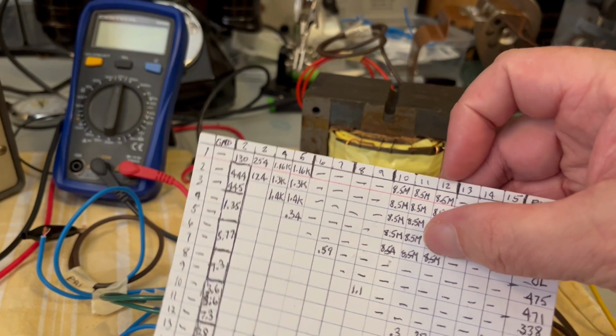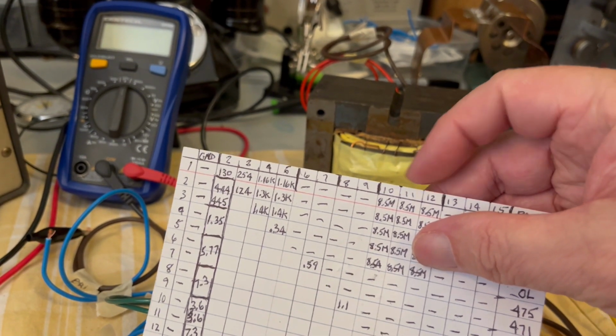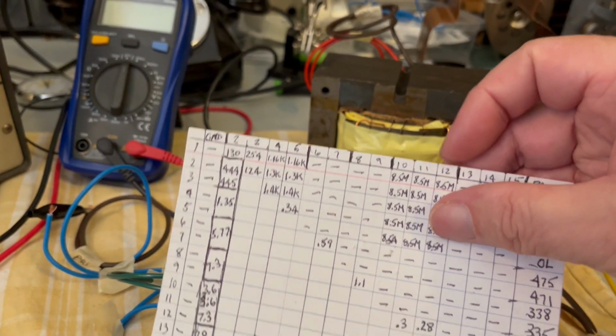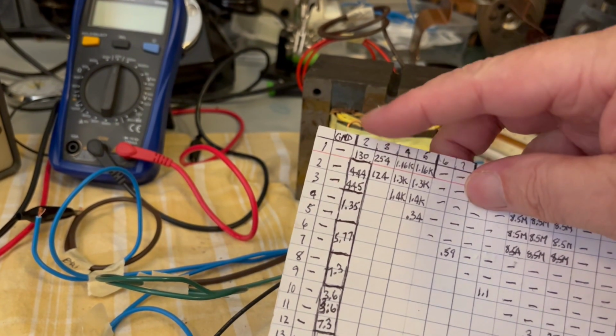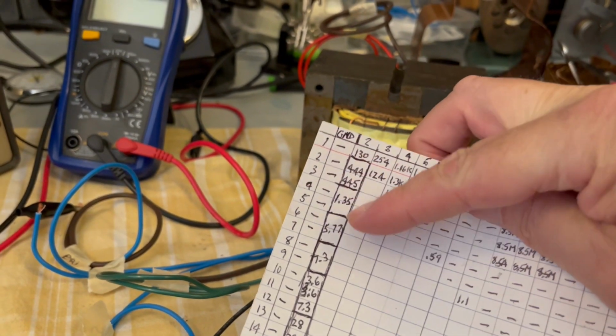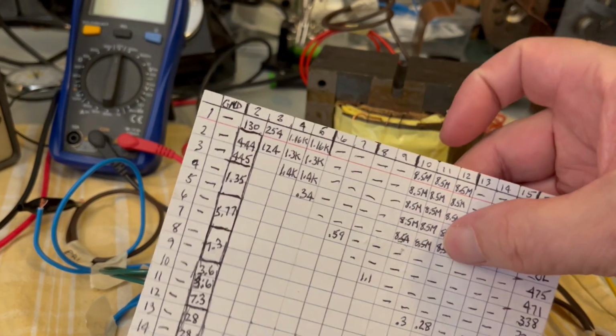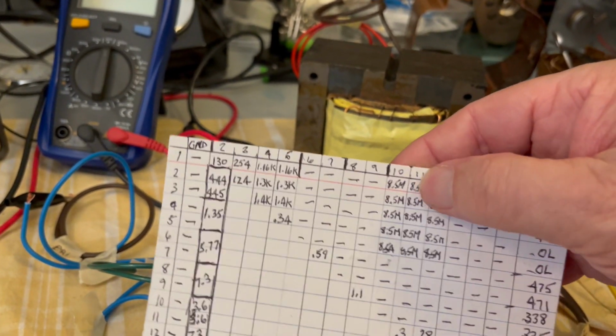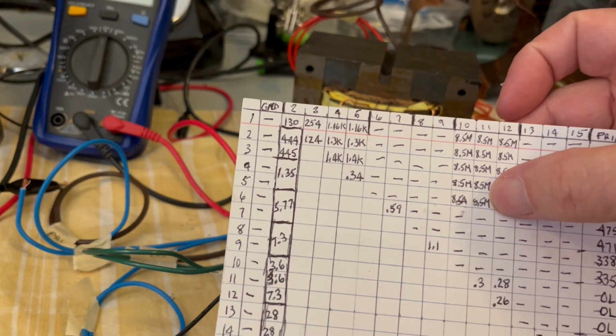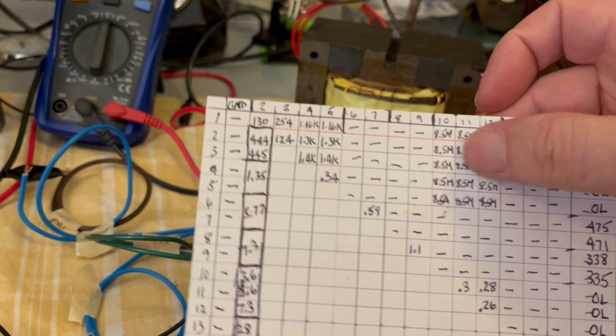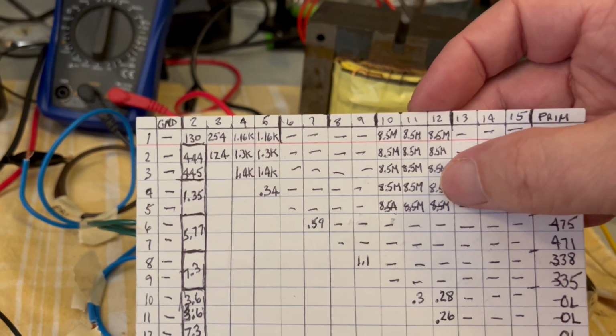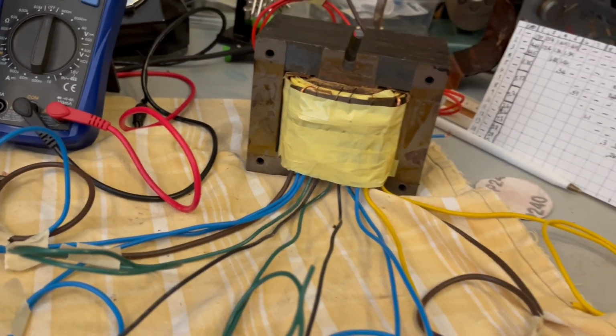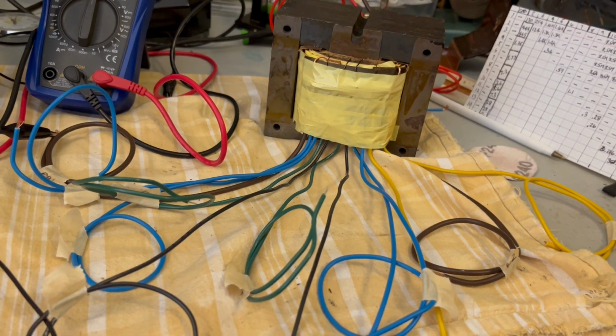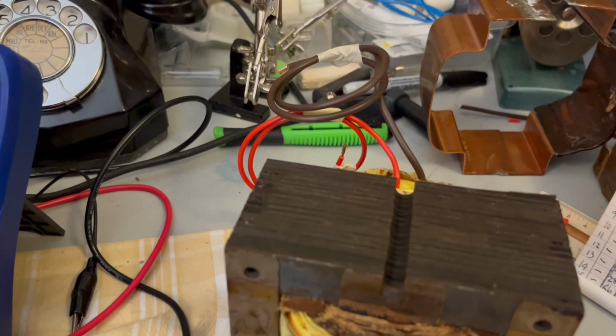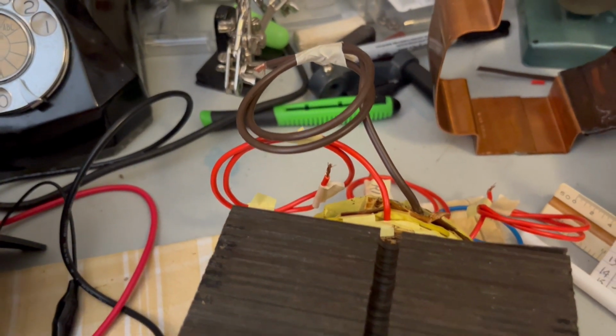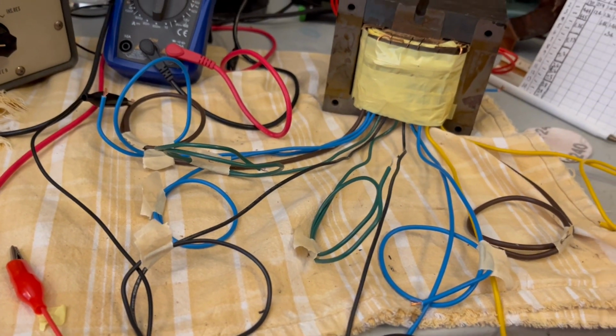These three leads right here are the ones with the suspect coil that we've been working with from the very beginning, and these five are the high voltage, and these five going this way are the high voltage. So we really shouldn't be reading anything in here on 10, 11, and 12. Especially not touching 1 through 5, and these are the readings that I had at first. So I'm going to duplicate that for right now, just to make sure I don't have any leads shorted. I'm not going to bore you with that, but basically I'm going to run through each lead and check it.